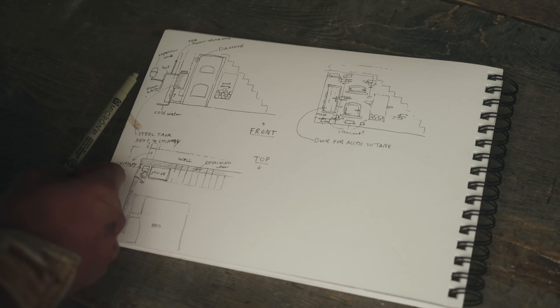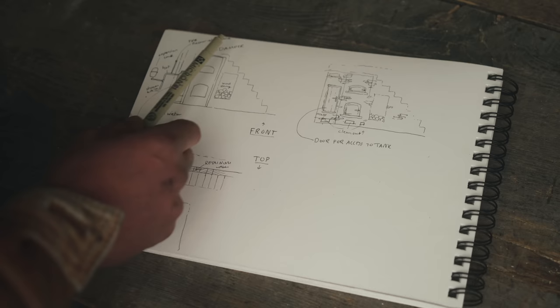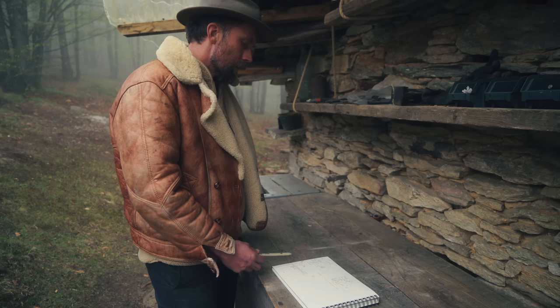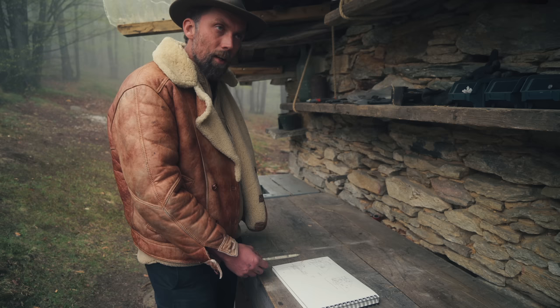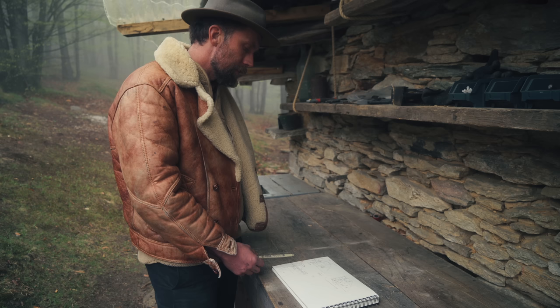Also, safety is quite minimal. You have an expansion tank for if the water gets very hot, and if it gets too hot, there's a pressure release valve that goes outside that can release the water, and then cold water will feed in to cool down the tank. So this is a much more simple system compared to the other one. Simpler to build, much cheaper as well, because you don't need all of the valves and all the tanks and all of the plumbing parts. It's just a steel tank and a few extra bits.